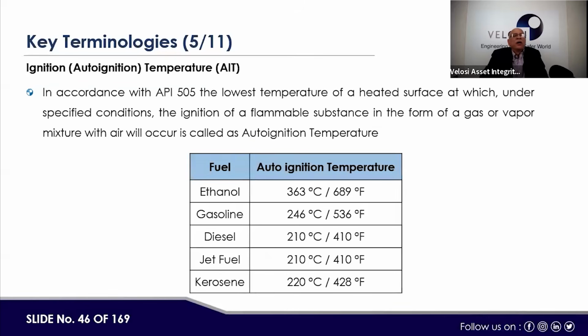Now the ignition or auto ignition temperature, AIT, in accordance with API 505. Some definitions we are bringing in from various codes so that we can get the relevant data and understanding. In accordance with API 505, the lowest temperature of a heated surface at which, under specified conditions, ignition of a flammable substance in the form of a gas or vapor mixture will occur is called the auto ignition temperature. Ethanol auto ignition is 363 degrees C, gasoline 246 degrees C, diesel 210, jet fuel 210, kerosene 220.